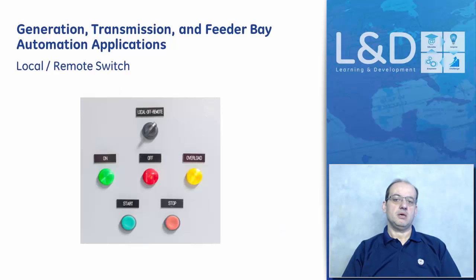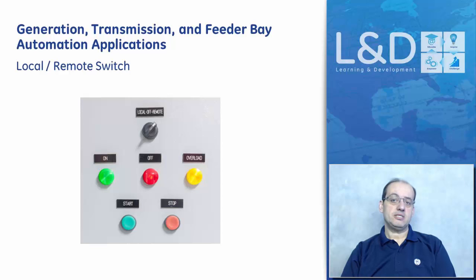In any bay or feeder bay, you might find a physical local remote switch. A soft local remote switch application provides a custom local remote enabling or disabling of substation control relays at the distributed sites. A master local remote switch located within the data concentrator RTU will control the enabling and disabling of the local remote switch function at the distributed sites.